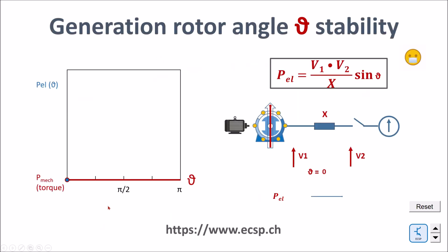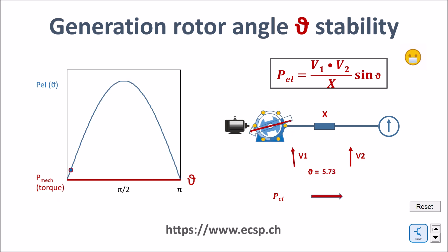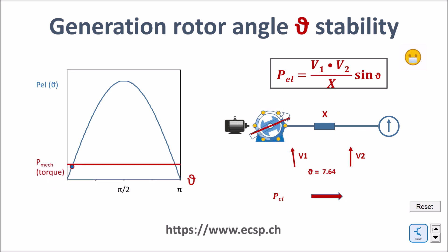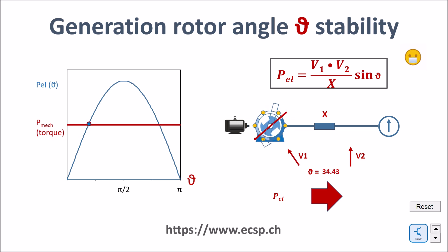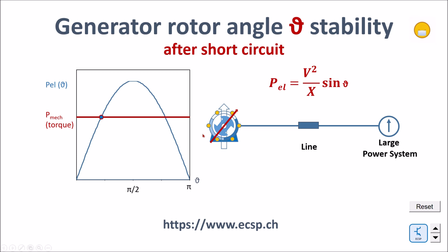Let me quickly reverse the process of synchronizing the generator to the grid, closing the breaker, and then slowly starting to push real power into the network. We are in the process of synchronizing, then we close the breaker, there is an oscillation, and then slowly we increase the mechanical power. The torque increases, and by doing so we increase theta, and by doing so we increase the real power fed from the generator to the grid. From now on I will show only the rotor angle, not the rotation animation.